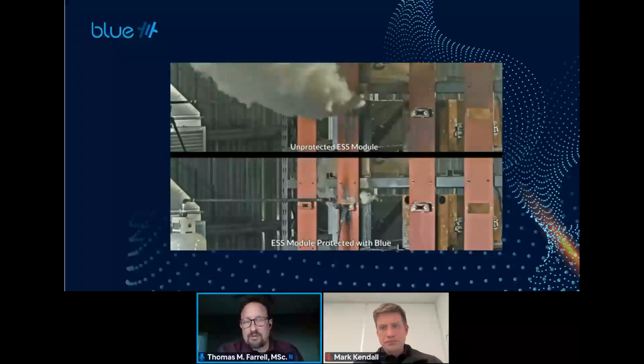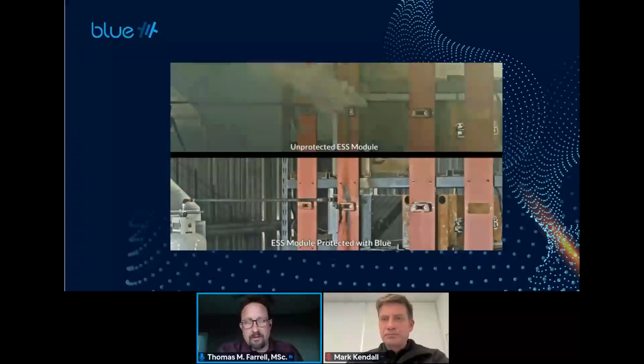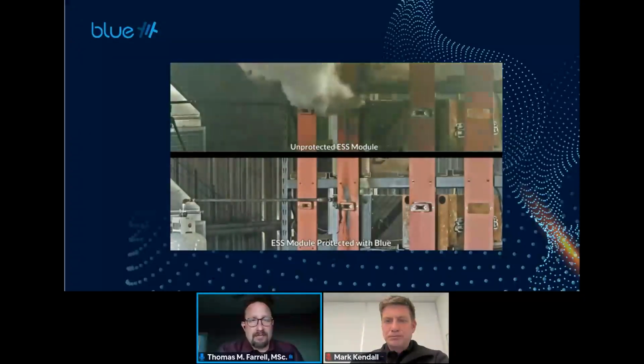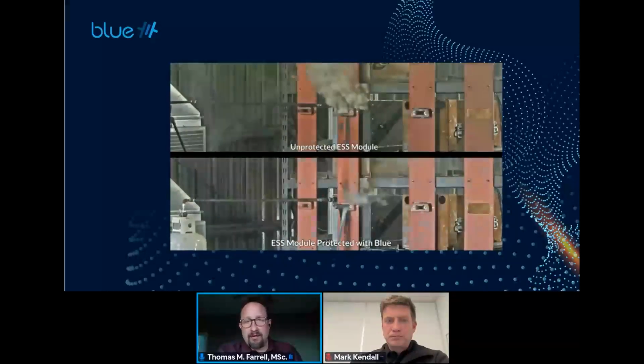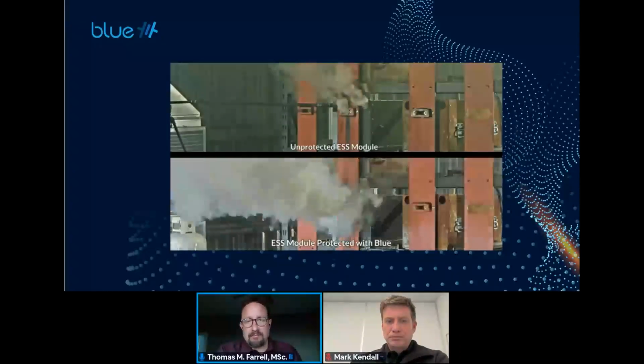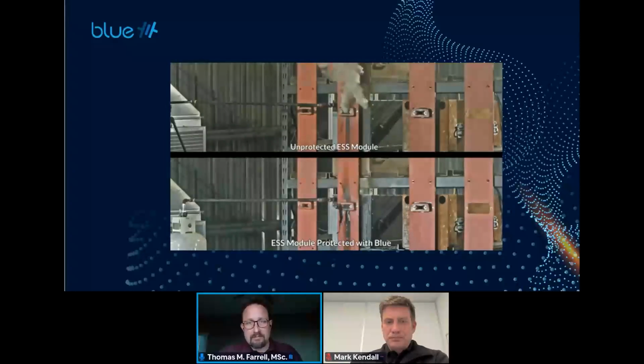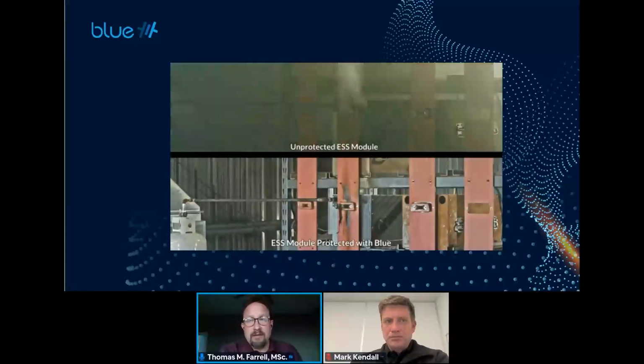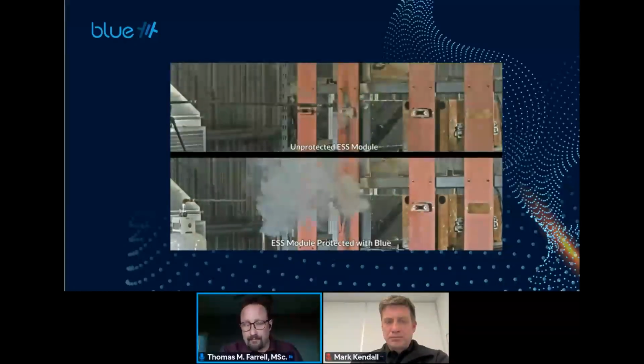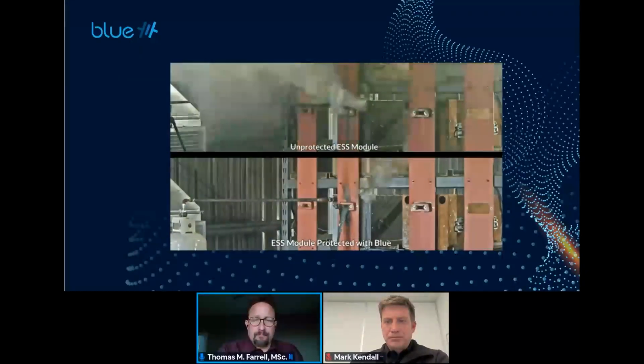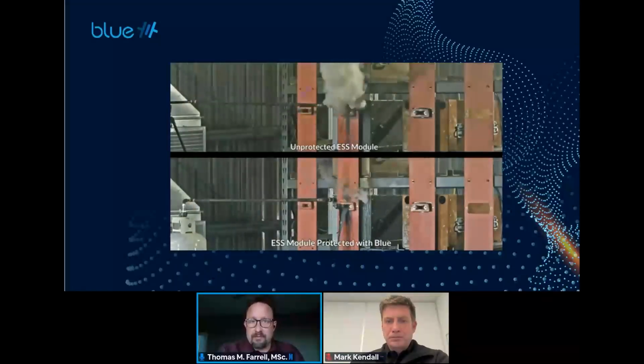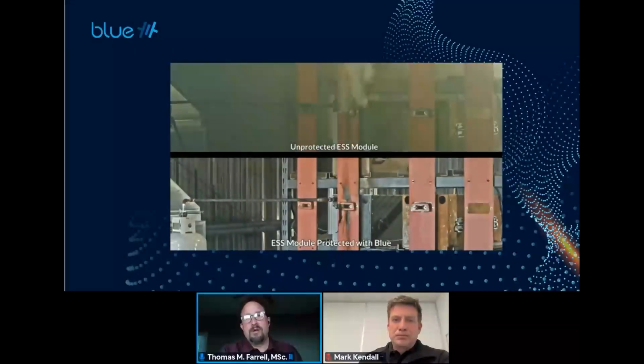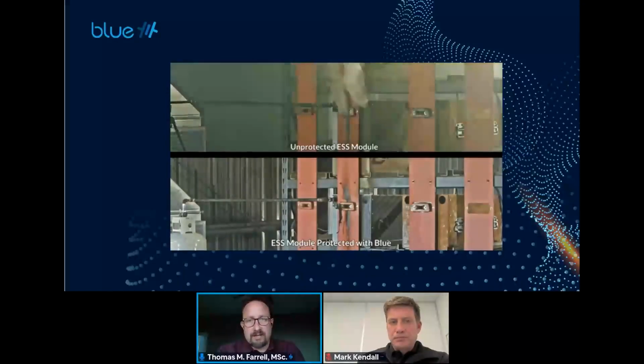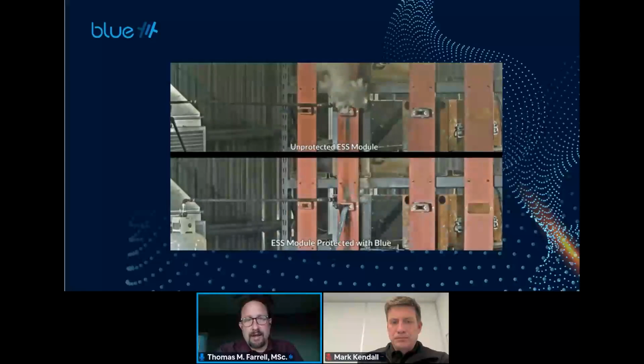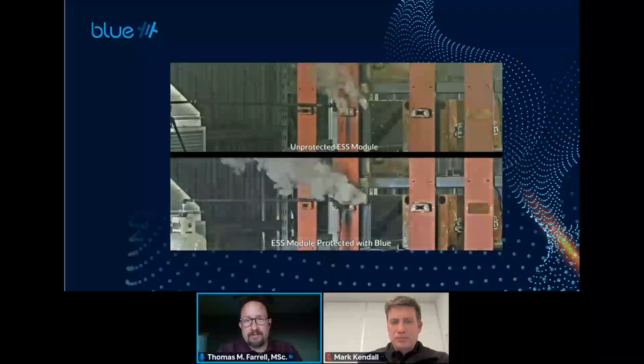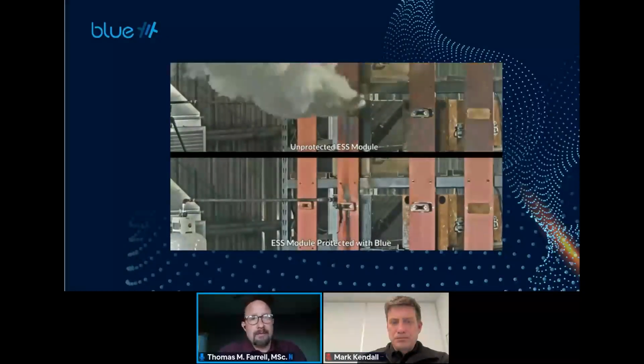Unfortunately, water causes electrical short circuits, and it does cause additional modules to go into thermal runaway. Then all the toxic things coming off this battery are no longer contained within the battery or in a small zone around it — they're spread throughout the area around the ESS installation, and tragically, likely into the ground and groundwater, which is a very bad thing. So this also represents an opportunity to provide thermal runaway management without causing additional environmental distress, or the need for a massive environmental cleanup effort to protect neighboring communities and water supplies.